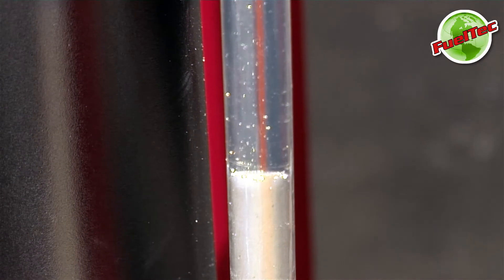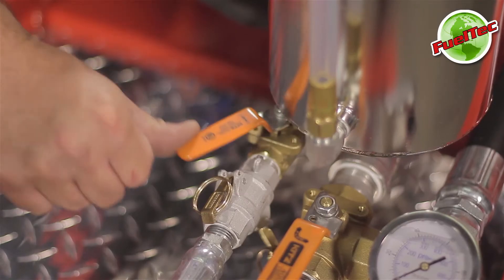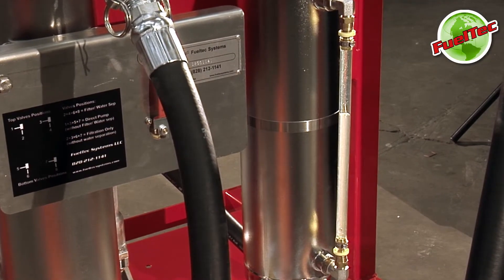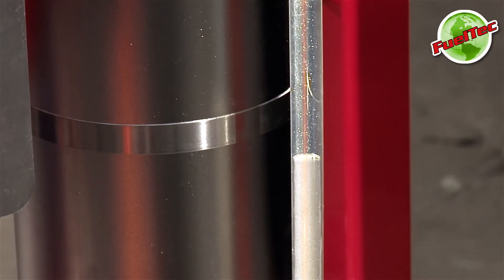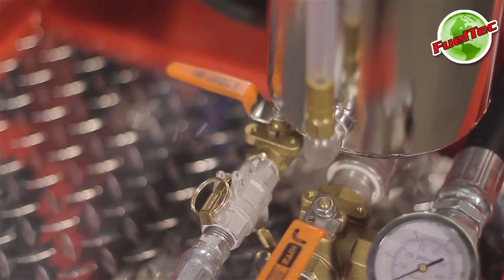Observe the sight tube as the water level rises. When the water level is halfway up the sight tube, open the separated wastewater discharge valve to drain the separator. When the water level is near the bottom of the sight tube, close the drain water valve.